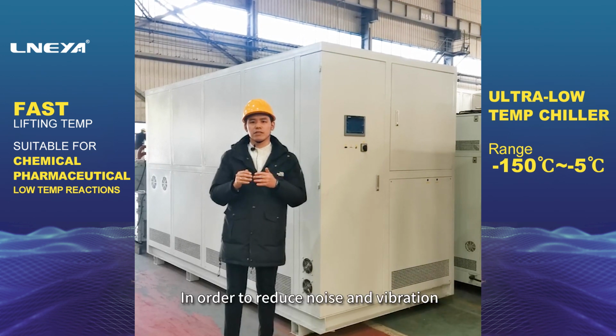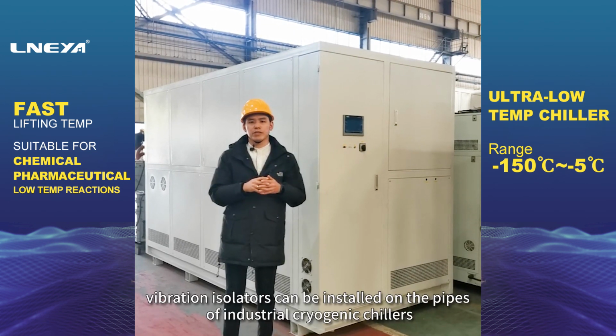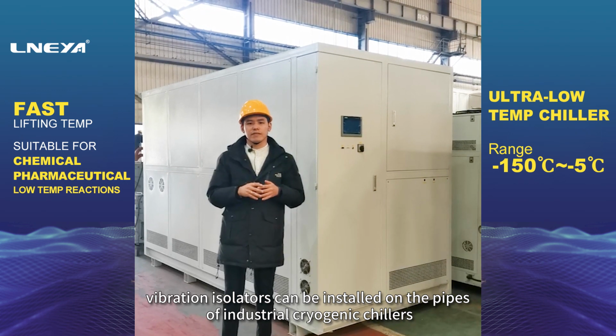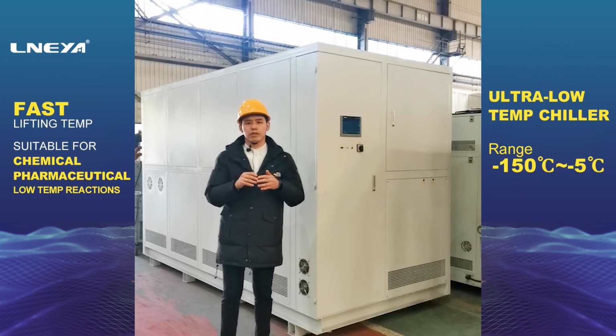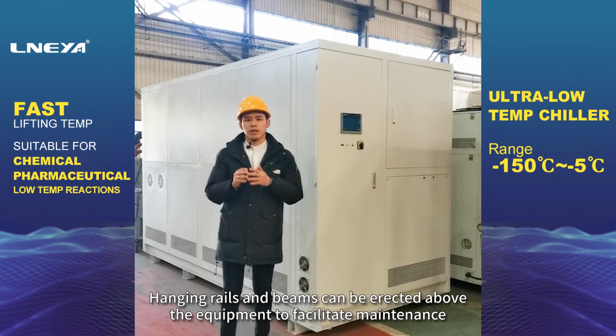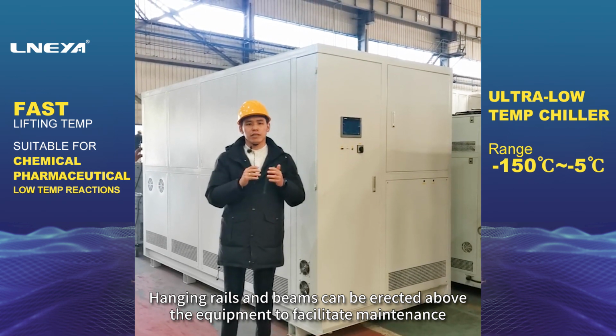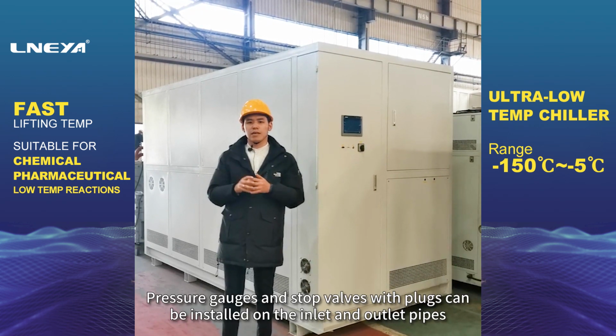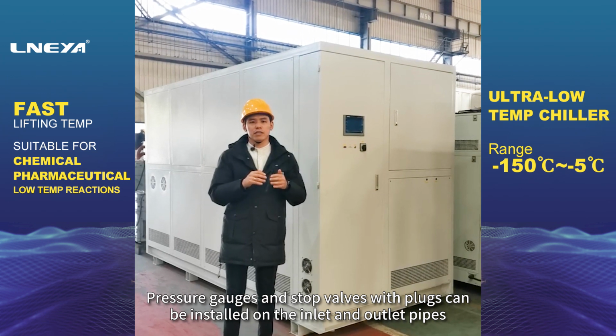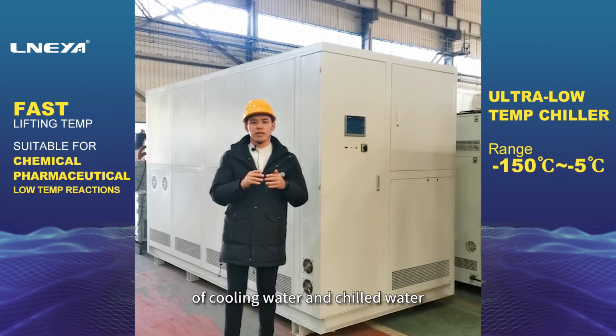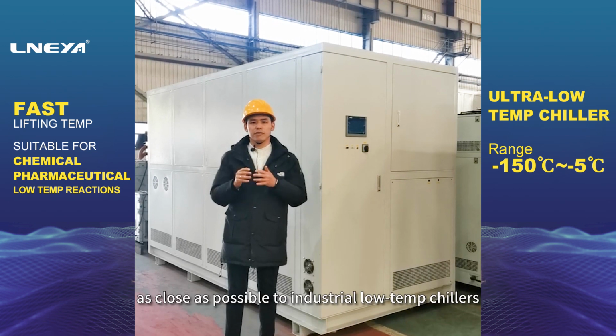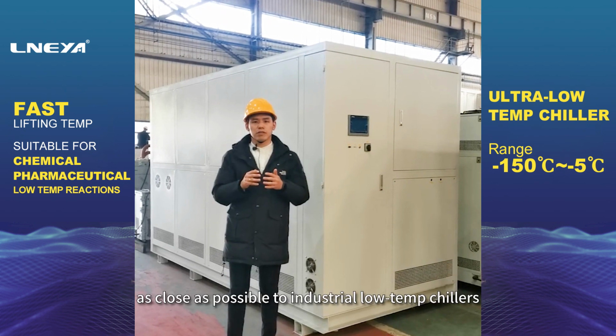In order to reduce noise, vibration isolators can be installed on the pipes of industrial cryogenic chillers. Hanging rails and beams can be erected above the equipment to facilitate maintenance. Pressure gauges and stop valves with plugs can be installed on the inlet and outlet pipes of cooling water and chilled water, as close as possible to industrial low-temperature chillers.